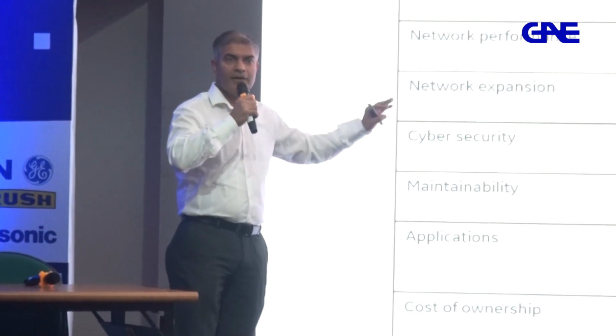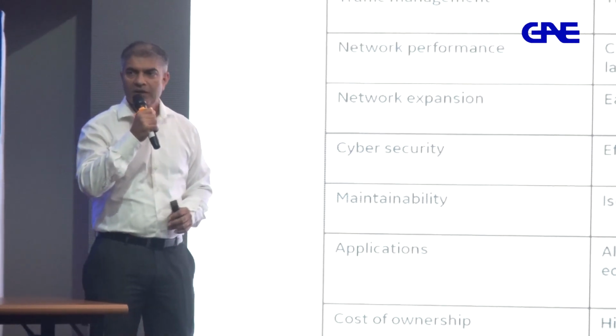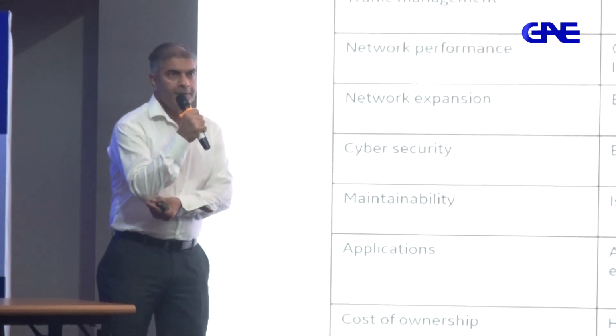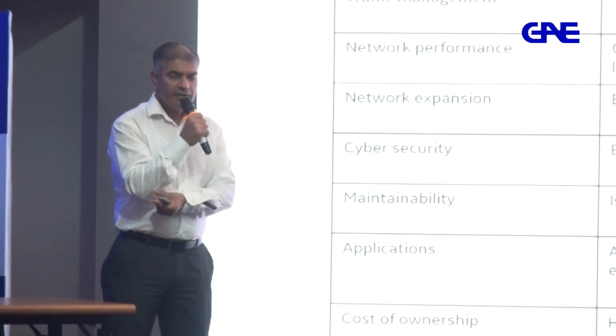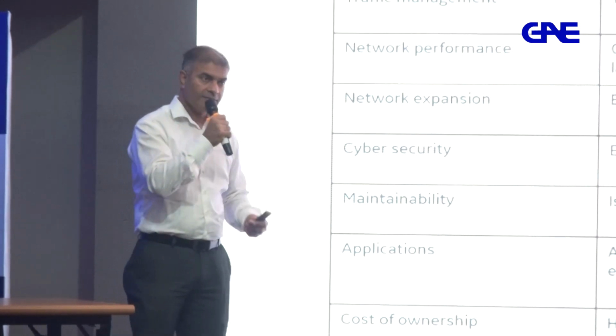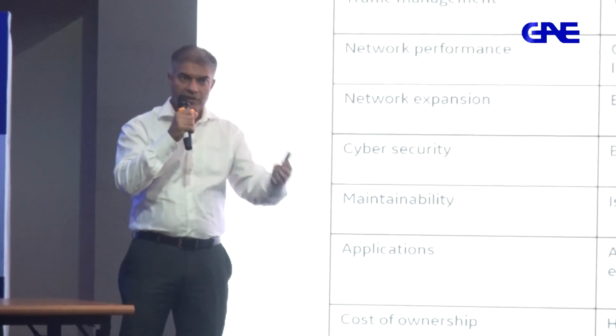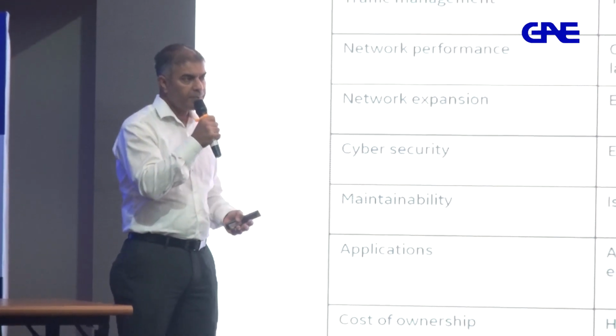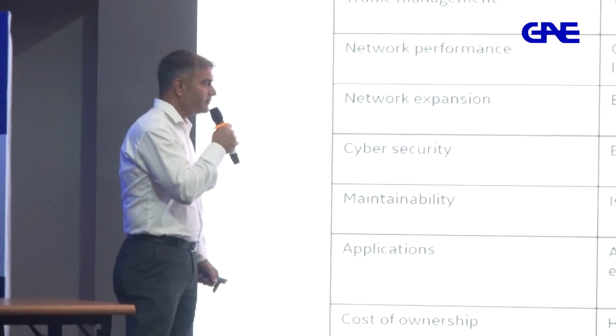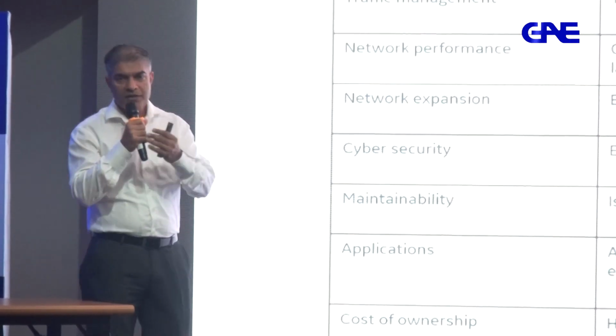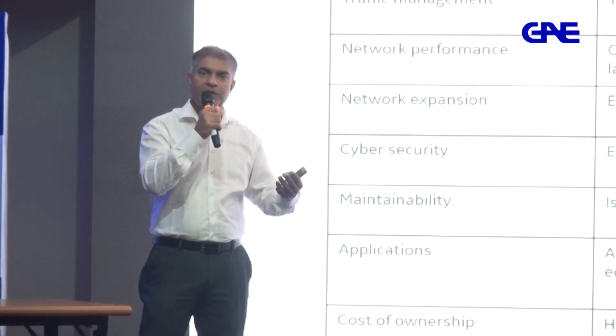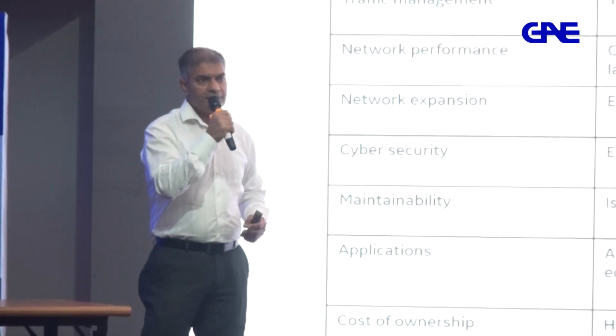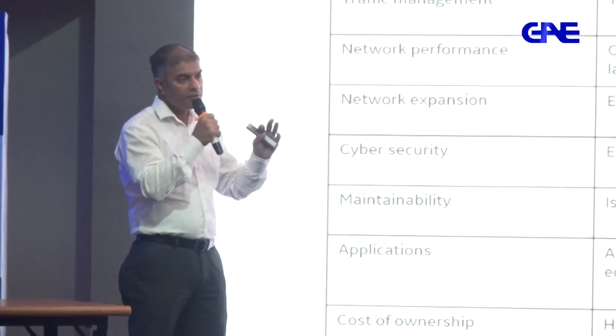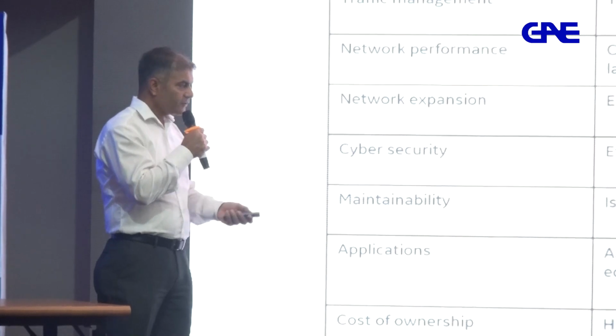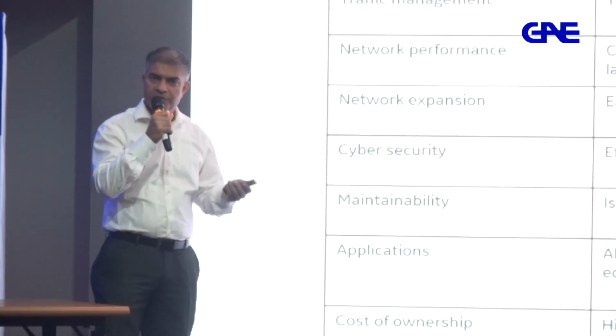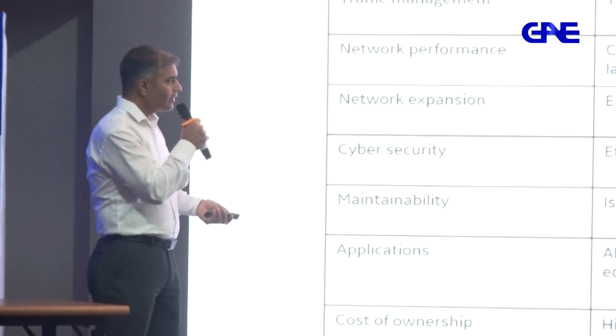PRP versus HSR: I don't want to tell you every point, but the main thing about HSR is that when you adopt HSR architecture, all your devices have to support HSR. Whereas with PRP, you can bring in different equipment, so interoperability and expandability are no problem. But with HSR maintenance, if you take one equipment into maintenance, your ring is broken, so your redundancy is gone. So all those things we need to consider very carefully. For big substations, for transmission level substations, PRP will give a lot of advantages.